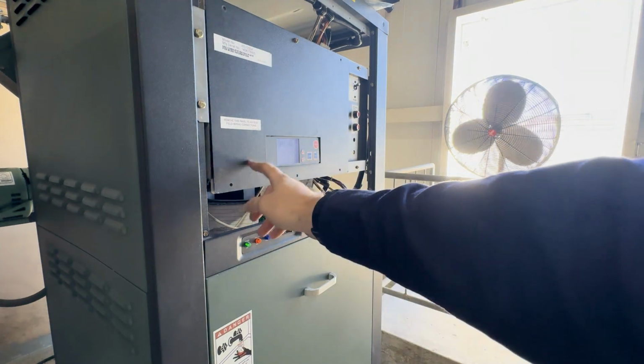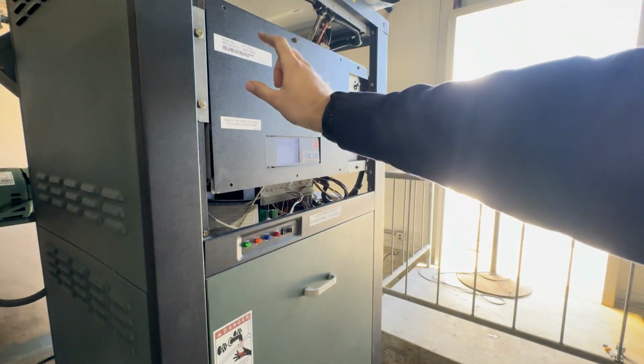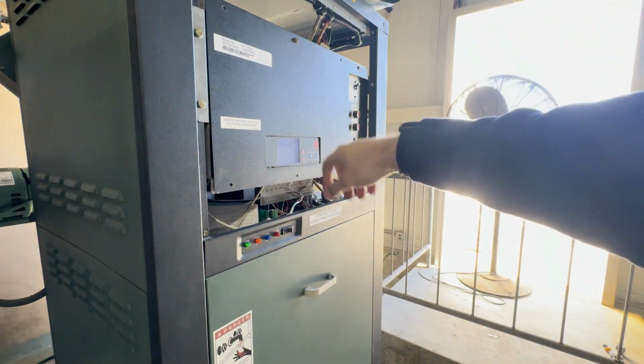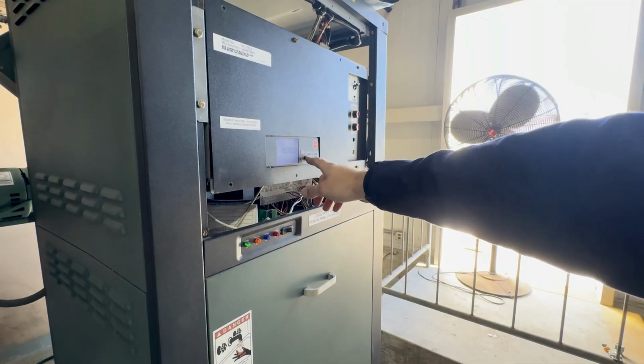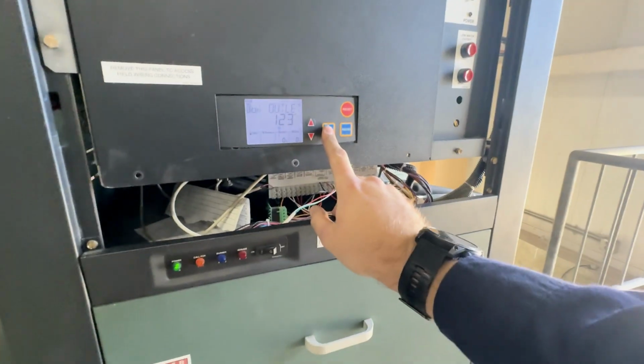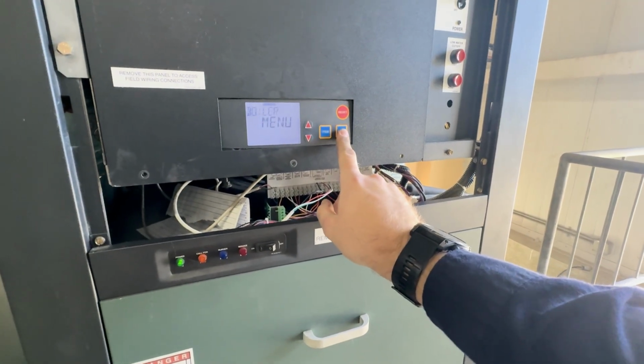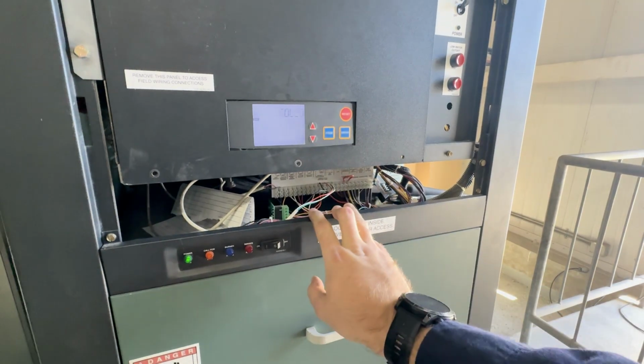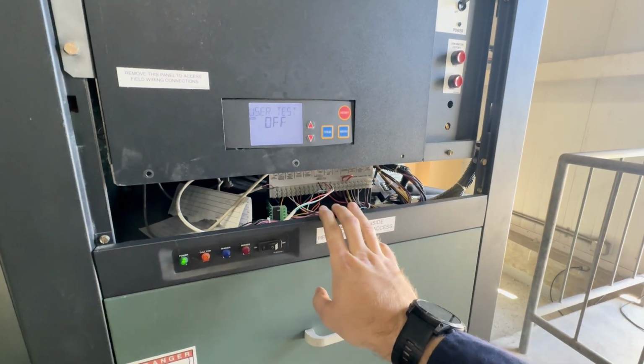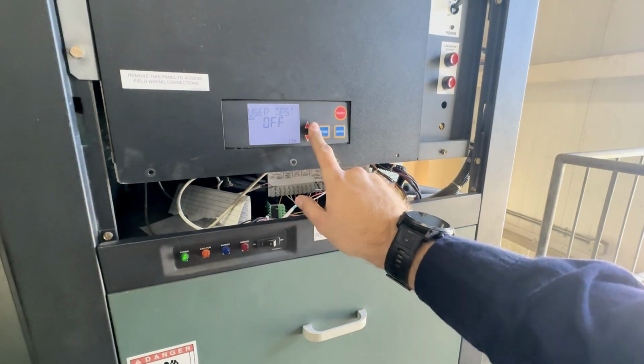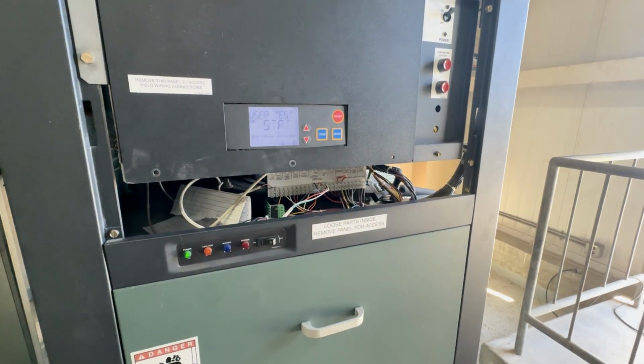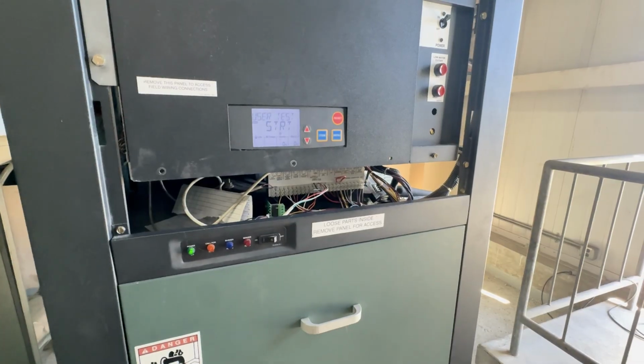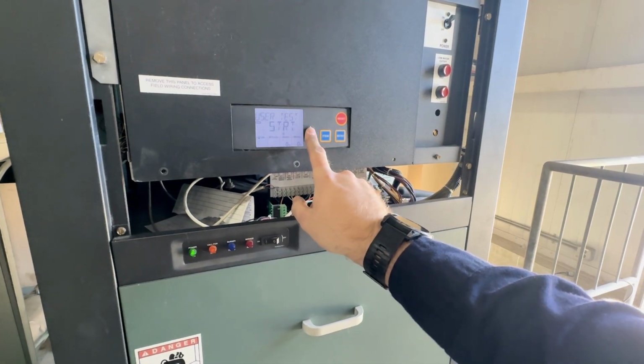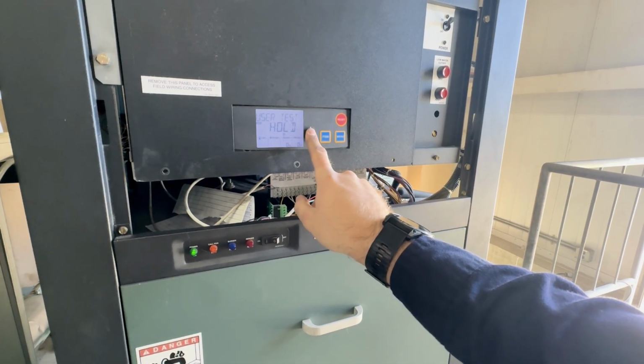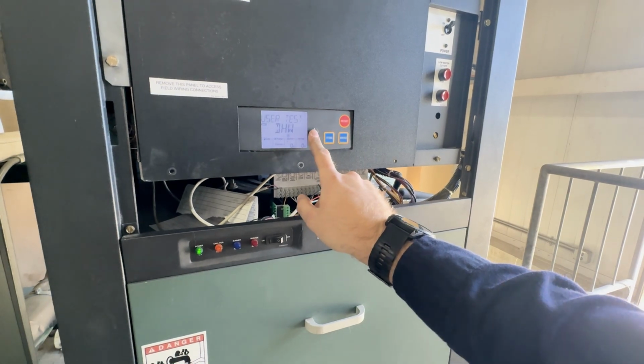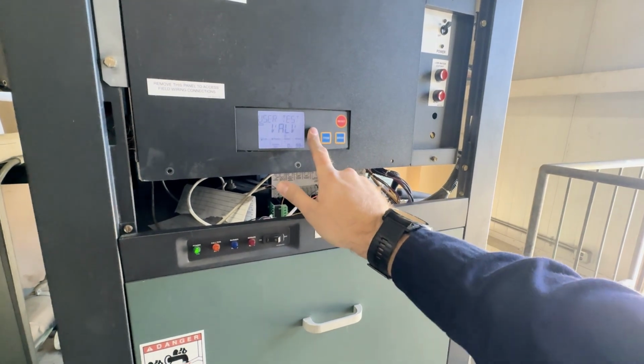On these Raypaks, you can navigate through the menu, assuming that you have the dip switch turned on that allows operator mode. You can navigate over here. Click the menu button: adjust, boiler, monitor, toolbox. Right here on the toolbox menu, the first setting is user test. To go ahead and cycle through, click on the up arrow. It's gonna go through start. We don't really care about all that. We're gonna skip through this. So to skip through that certain test, you're gonna double press the up arrow.